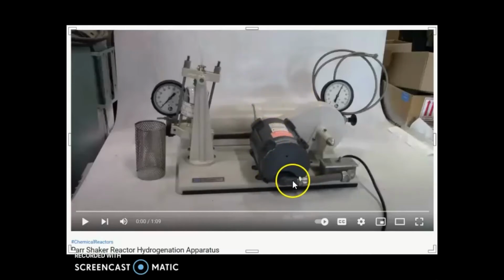Explosion-proof also means that it is hardwired. You see this cable here? This one still has a plug somewhere, but usually when you have an explosion-proof installation, there's no plug. An electrician has come in and connected it to the wiring of the building with no plug, because the plug itself becomes a spark source when you plug it in and unplug it. So that's what's meant by explosion-proof.